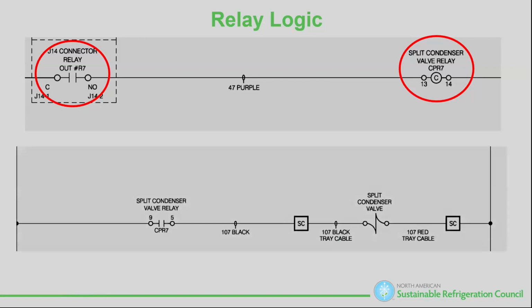So then I go to the split valve, CPR7 - always notice CPR7. The OEM is going to tell me if I have a coil called a relay, a contactor, and it's labeled CPR7. Turning a coil on by itself does nobody any good. I have to go find it. It may be later on that page, it may be 3 pages over on the wiring diagram. It just depends on how it's laid out.